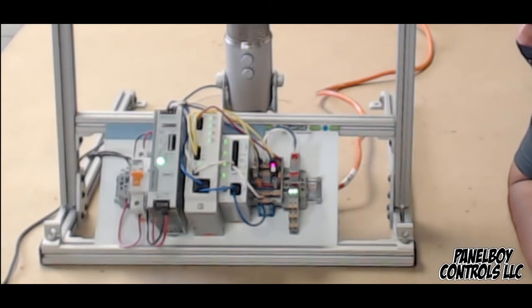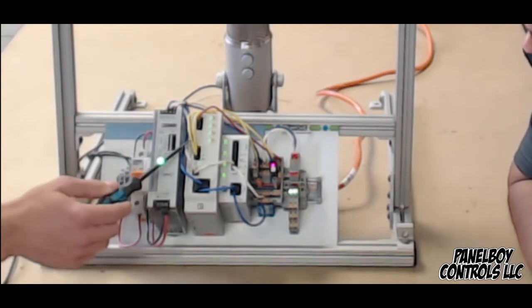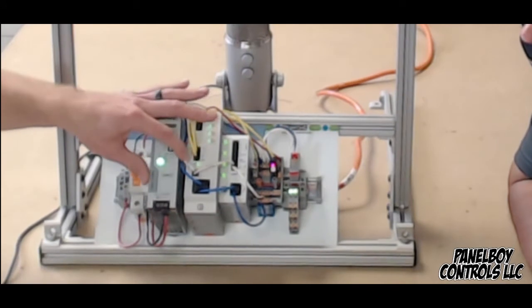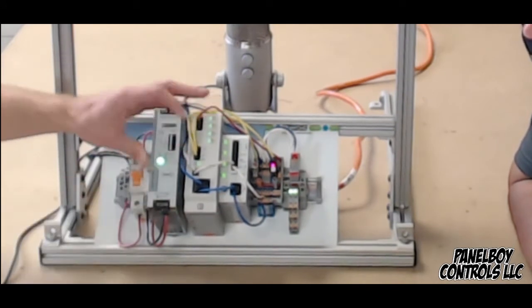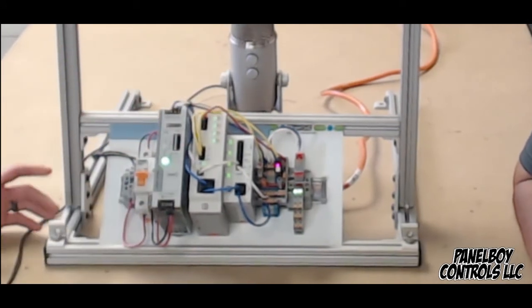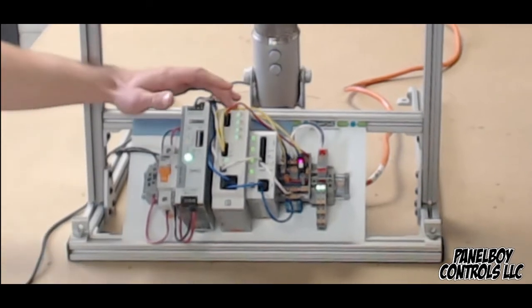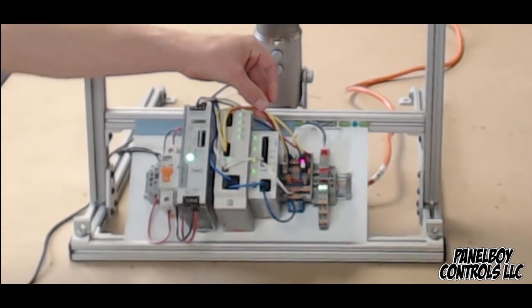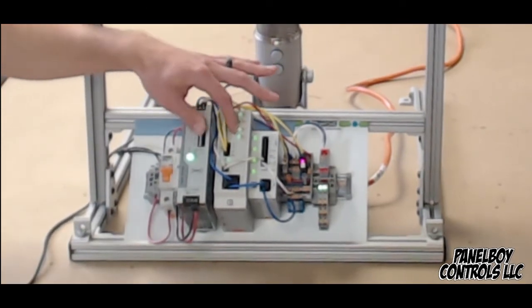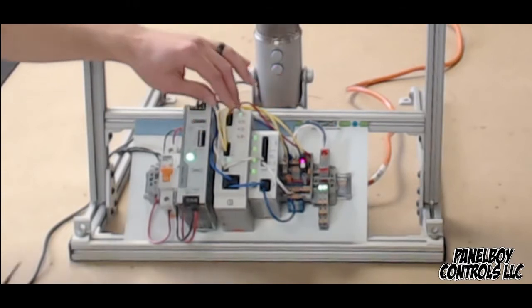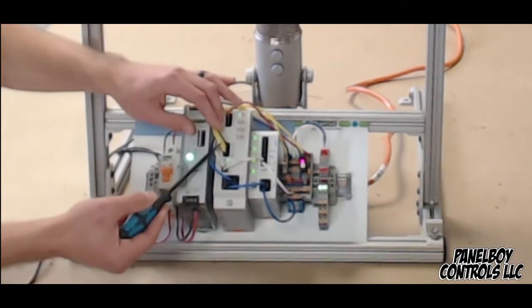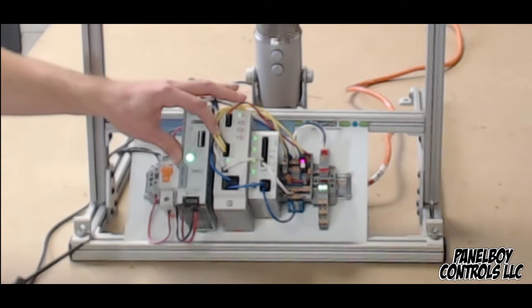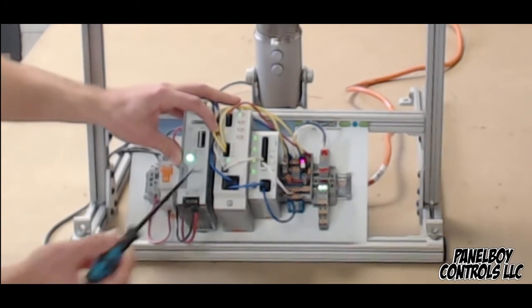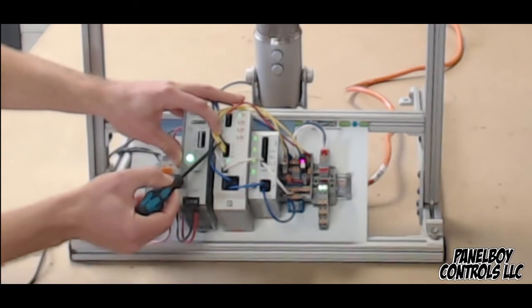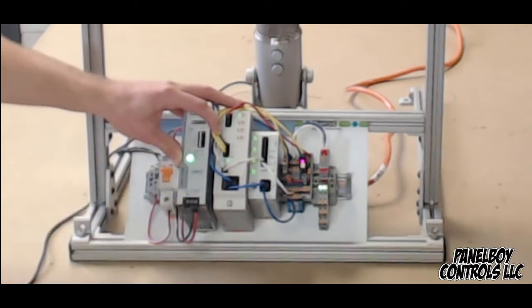I can show you some of the cooler features of this. There's a couple things to note on the back: there's a DC OK indicator to let you know your input voltage is good. I've got this wired up with a load coming off the first channel, and down here is where the status and important information back to your PLC would typically go.